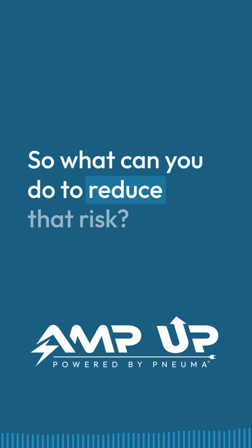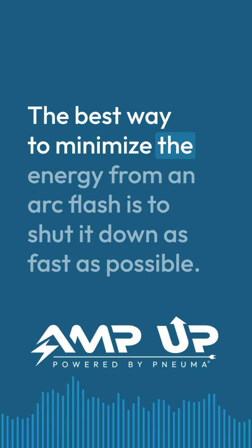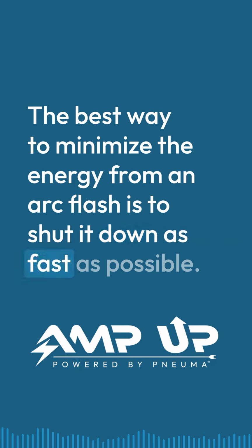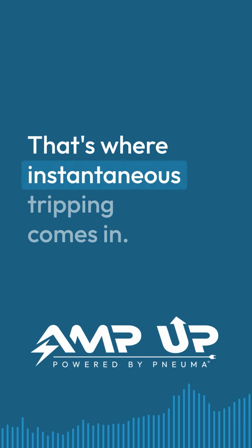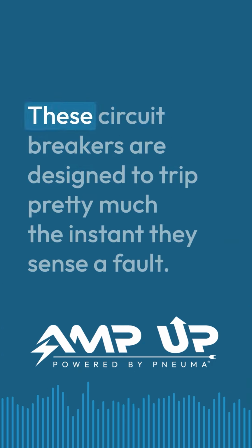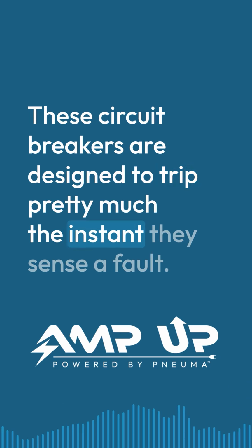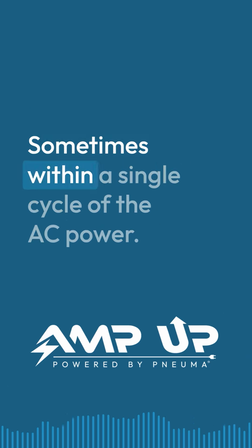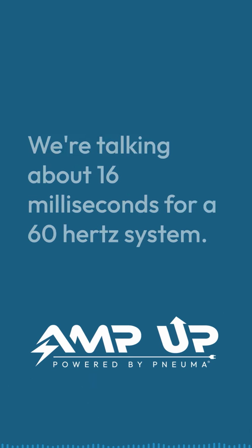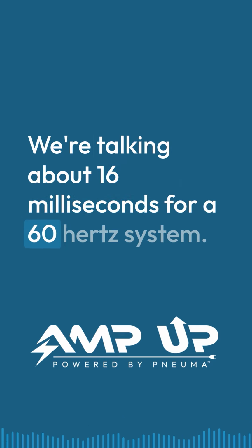So what can you do to reduce that risk? The best way to minimize the energy from an arc flash is to shut it down as fast as possible. That's where instantaneous tripping comes in. These circuit breakers are designed to trip pretty much the instant they sense a fault, sometimes within a single cycle of the AC power. We're talking about 16 milliseconds for a 60 hertz system.